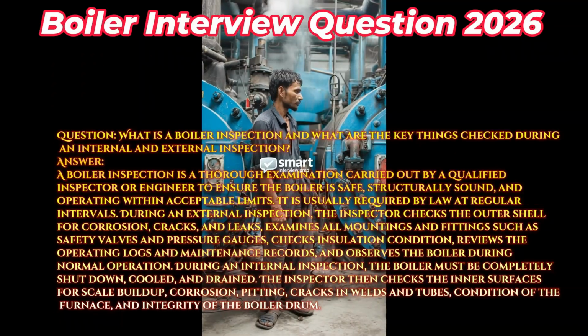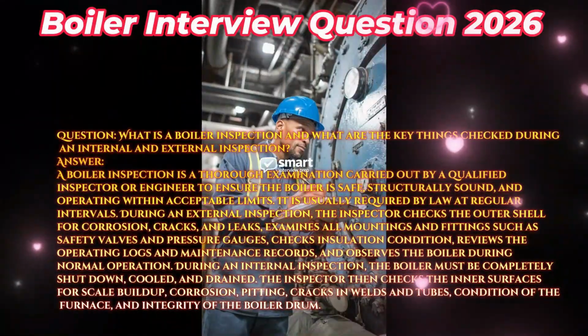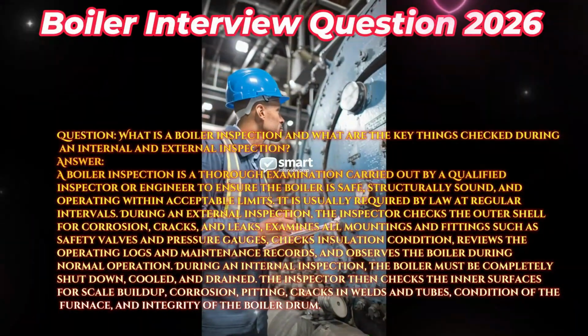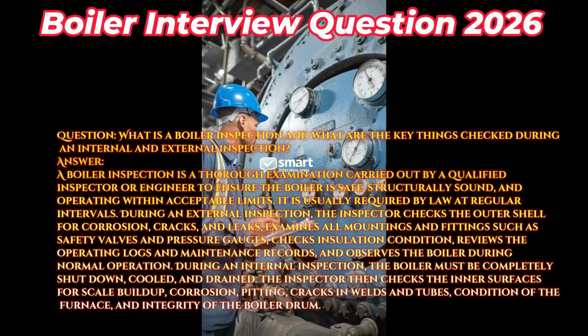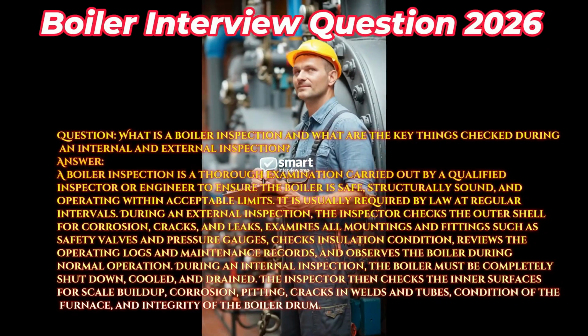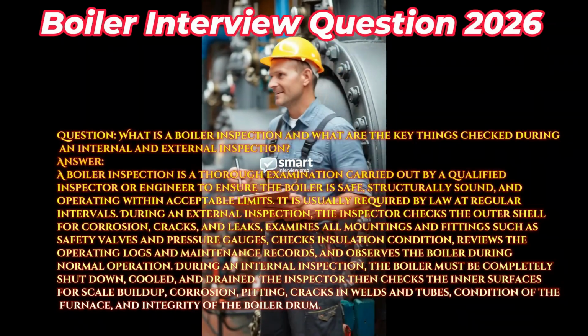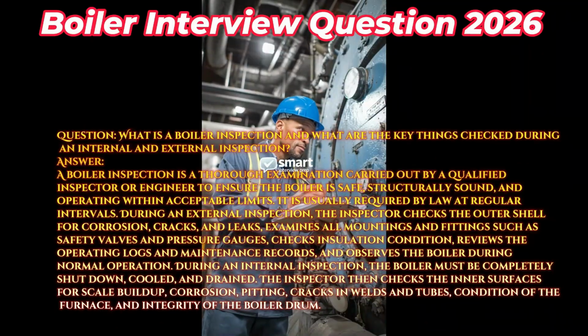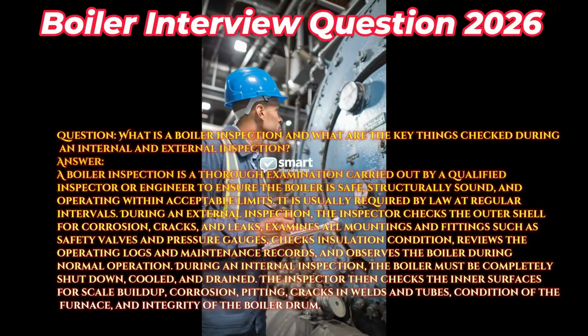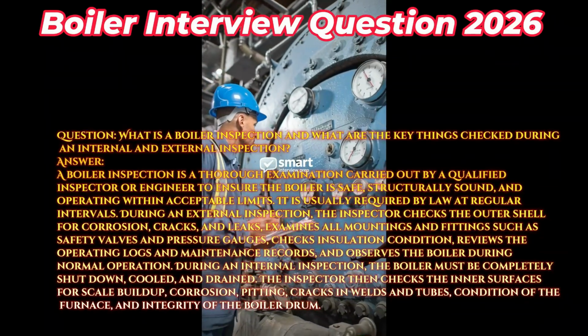boiler during normal operation. During an internal inspection, the boiler must be completely shut down, cooled, and drained. The inspector then checks the inner surfaces for scale buildup, corrosion, pitting, cracks in welds and tubes, condition of the furnace, and integrity of the boiler drum.